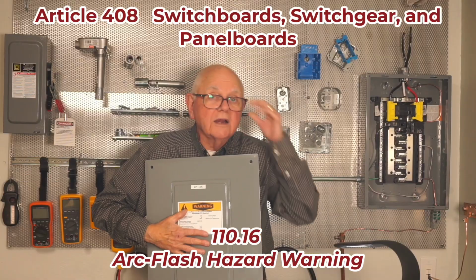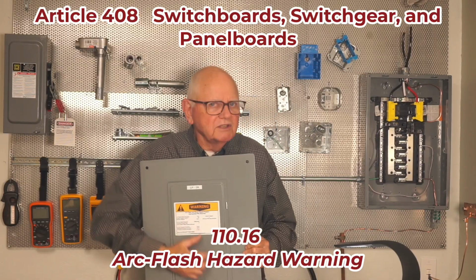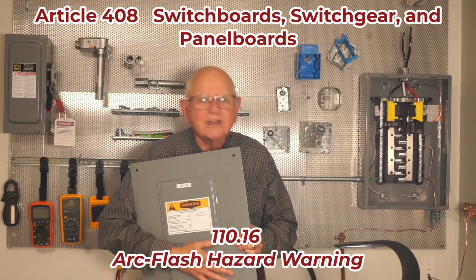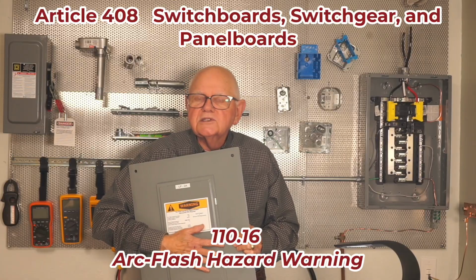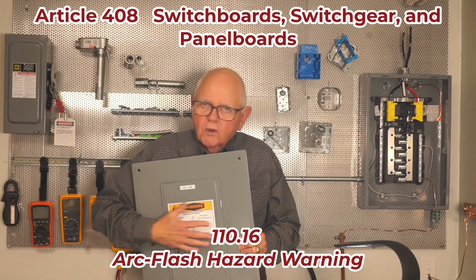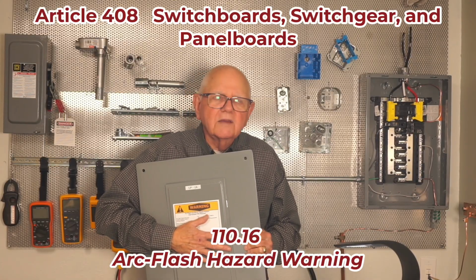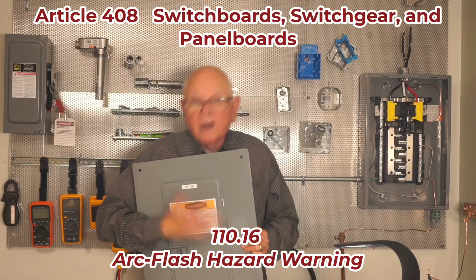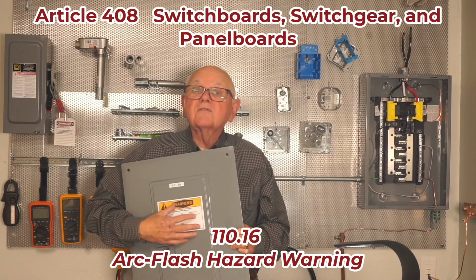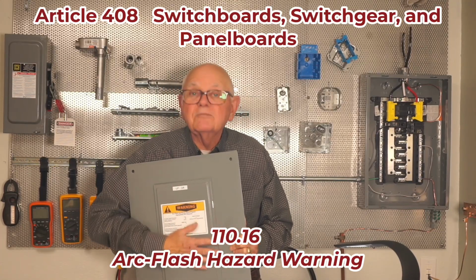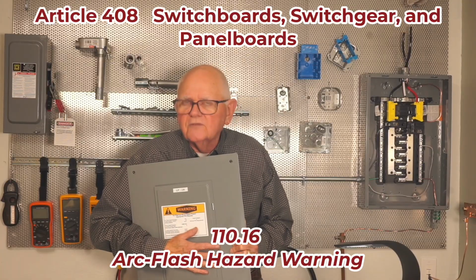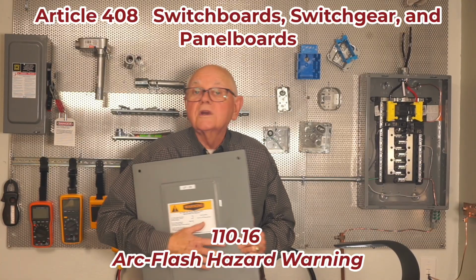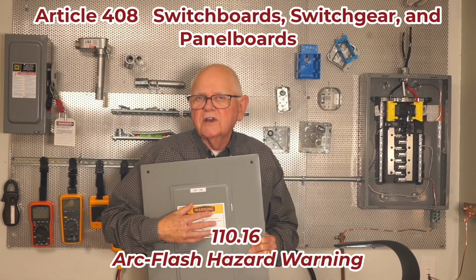It's not required in 110.16, at least not in the 2023 code that we're talking about today. But 110.16 says that equipment that's likely to require examination, and panelboards are included, in other than dwelling units, has to have an arc flash warning label, and it sends us to the NFPA 70E standard. The informational note says that's where to find what information has to be on the label.